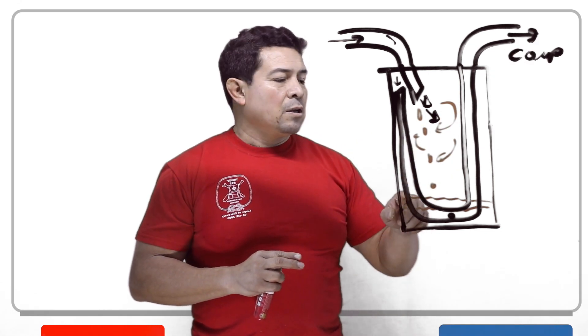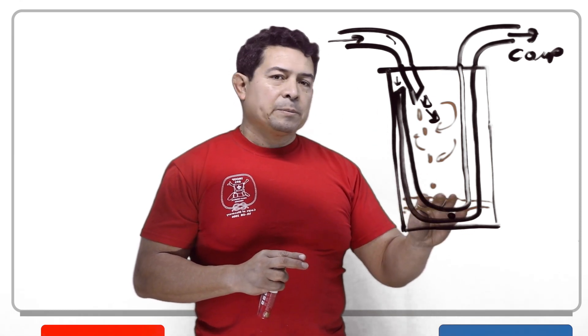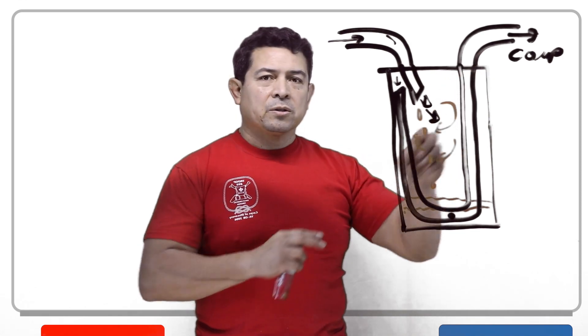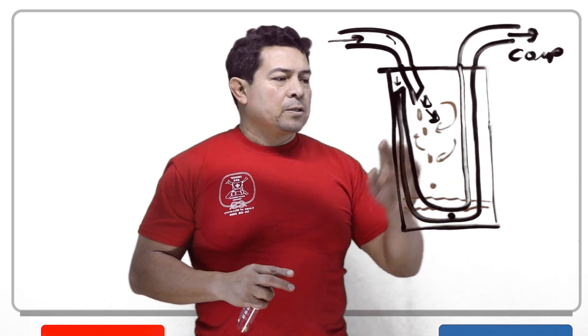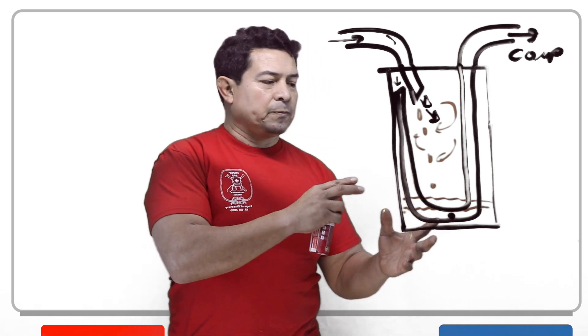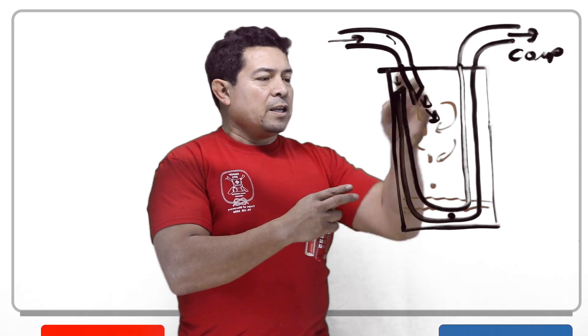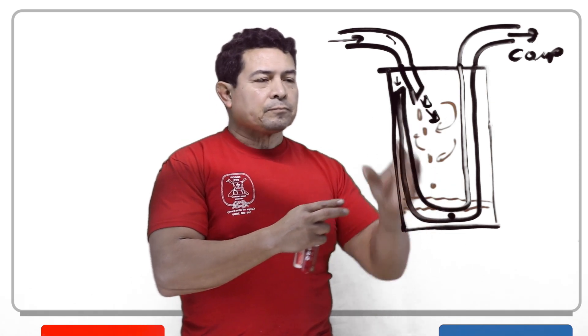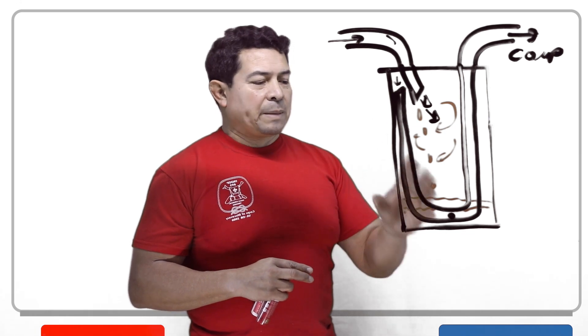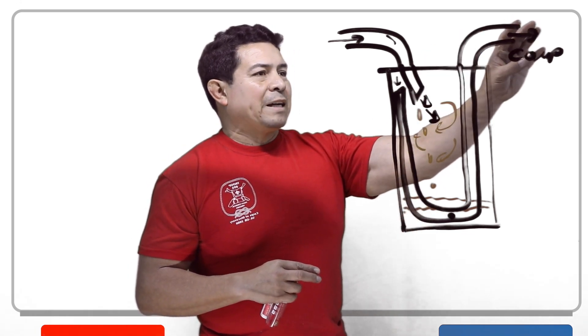So you are returning all of the oil that might be traveling through the system, and some of the liquid refrigerant, back to the compressor — but all as a mist. I always like to tell students that this is like a safety device for the compressor. It's a safety device so that no liquid gets to the compressor, trapping liquid in here. This is your accumulator — it traps liquid refrigerant so you only have vapor going back to the compressor.